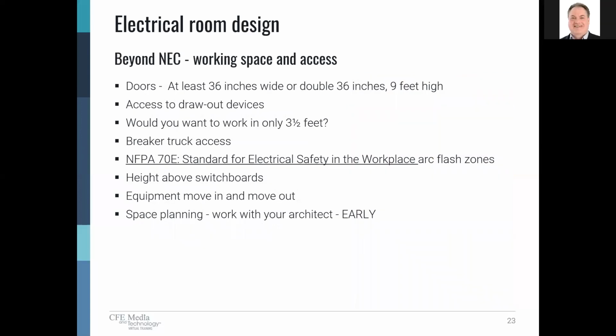Okay, let's talk a little bit about beyond the NEC. The NEC is the minimum required that you have to do as a design professional. It's not necessarily the best practice or even the most safe approach to do design, but it is the minimum. So we have a couple of recommendations here when we talk about electrical room design. First, James just touched on the code required minimum dimensions for the doors, but really, when you look at some of the sizes of the switchgear or switchboards, we recommend 36 inches wide or really double 36-inch wide doors that are 9 feet high. You've got to be able to get this gear or switchboards in and out of the room easily for maintenance and future replacements.